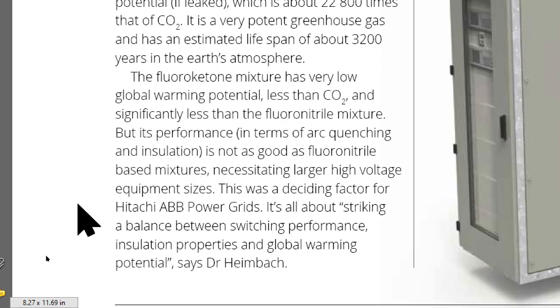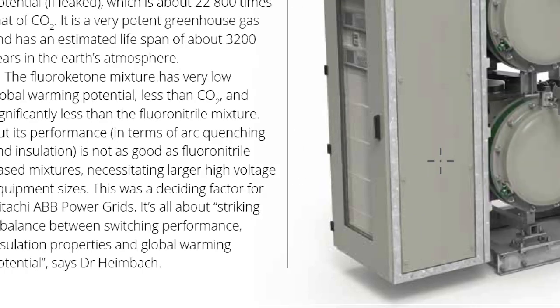The fluoroketone mixture has a very low global warming potential, less than CO2, and significantly less than the fluoronitrile mixture. But its performance in terms of arc quenching and insulation is not as good as fluoronitrile-based mixtures, necessitating larger high-voltage equipment sizes. This was a deciding factor for Hitachi ABB Power Grids. It's all about striking a balance between switching performance, insulation properties, and global warming potential, says Dr. Heimbach.